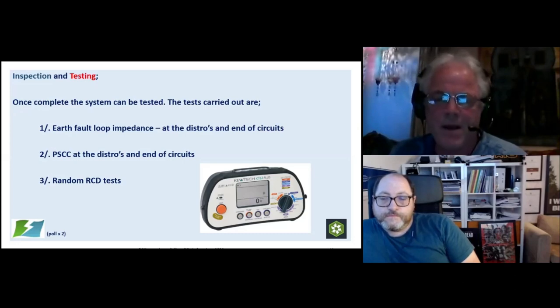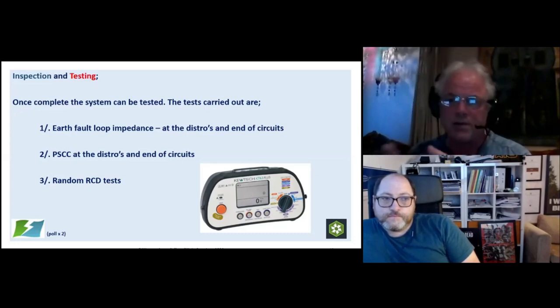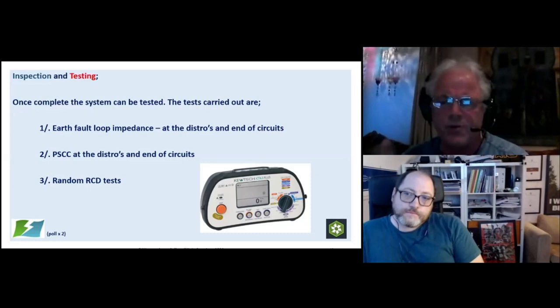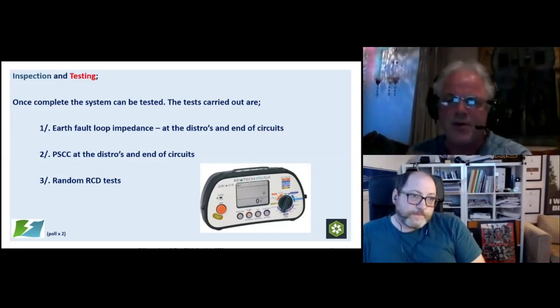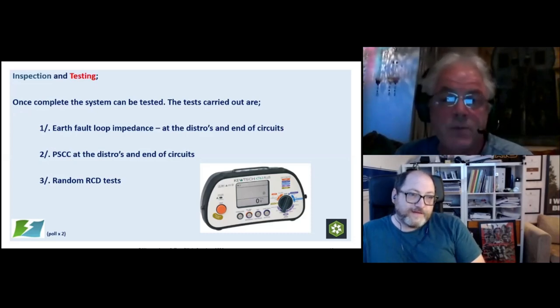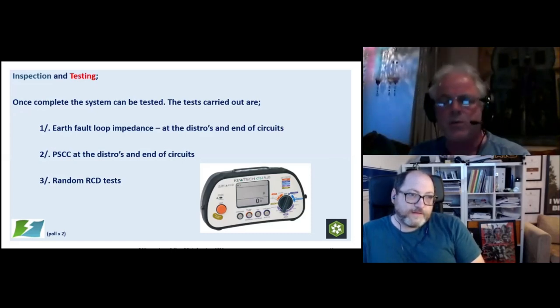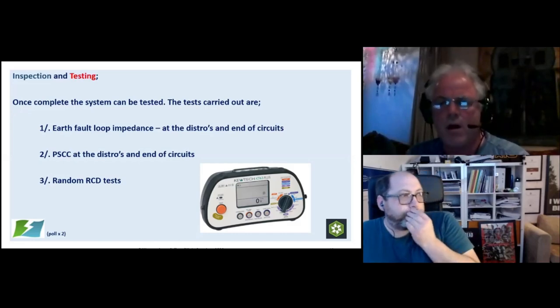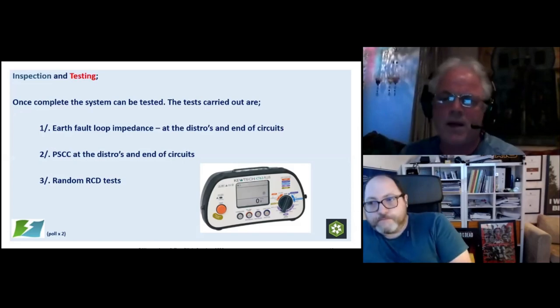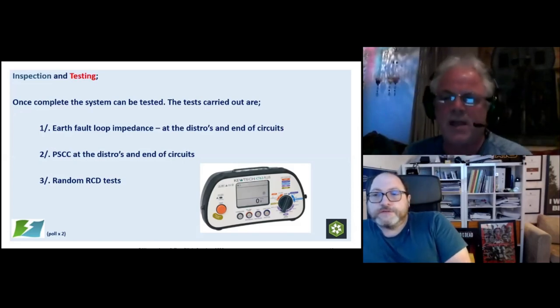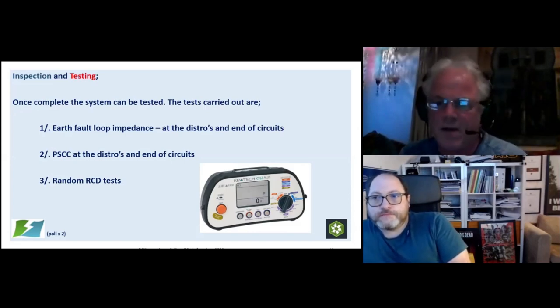Yeah. And sometimes, especially with the digital ones where you use the press buttons, you see the number 30 come up, you think, oh, I've set that at 30 milliamps. What you've actually done is you put a 30 second delay in. And this is one of the issues. So with the larger size RCDs and RCBOs in the distro, I will tend to test those. Because I want to check that I've done the selectivity and I've got the actual rating correct on my adjustment.